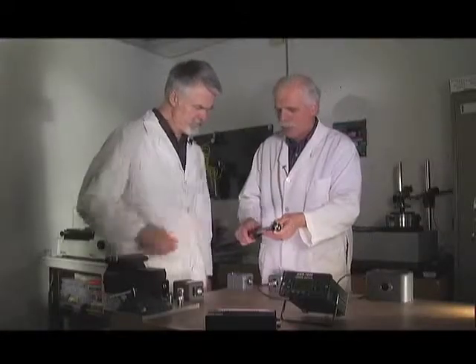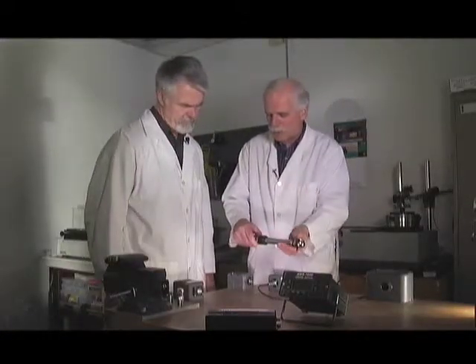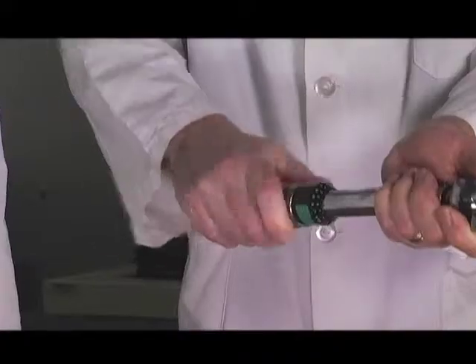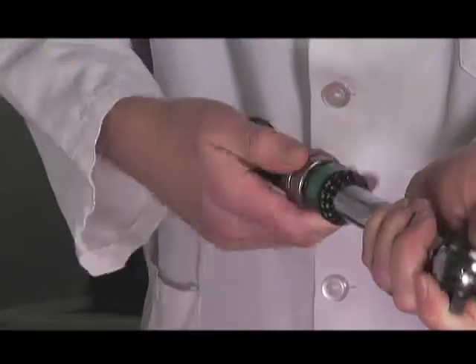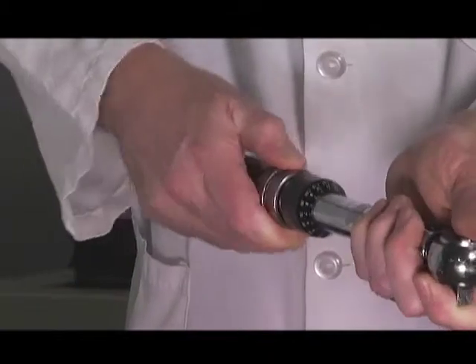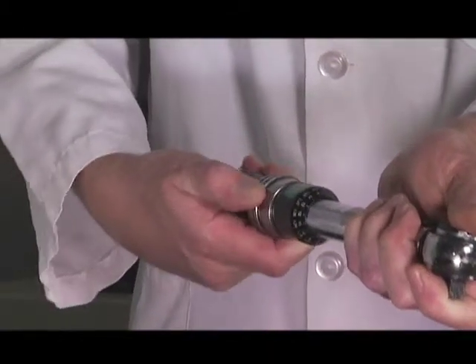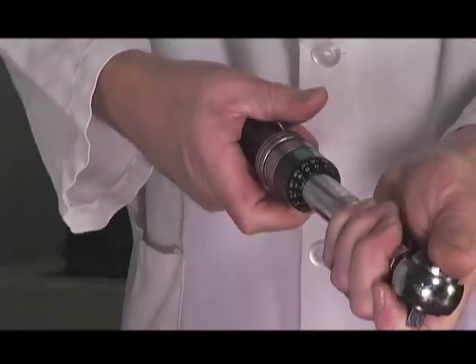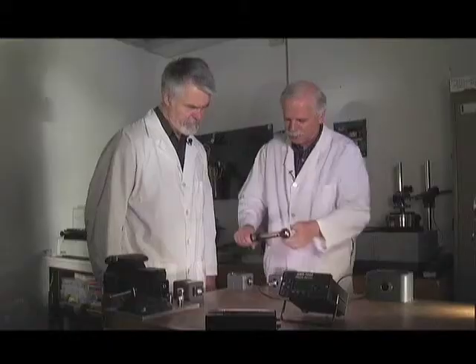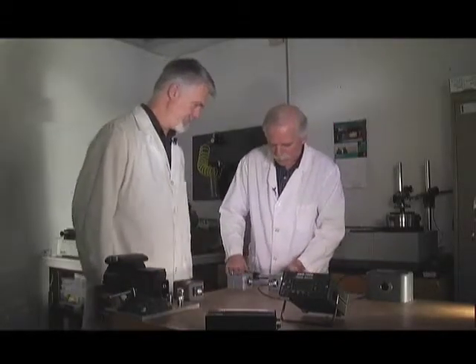And how do you adjust this? In this case, you pull on the little metal bezel and you just dial it right into whatever number you're after. In this case, we'll start off just dialing it into 50, looks like 55 inch-pounds. And we would put it on the calibrator.